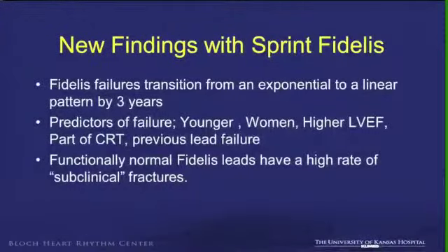And there have been other studies which have been done since then till now, and these are the newer additions to understanding the Sprint Fidelis fracture. And what we know at this time is the exponential increase in the fracture has actually plateaued and become linear after 3 years. And there are other predictors, so again, retrospective studies or observational studies, with whatever limitations.